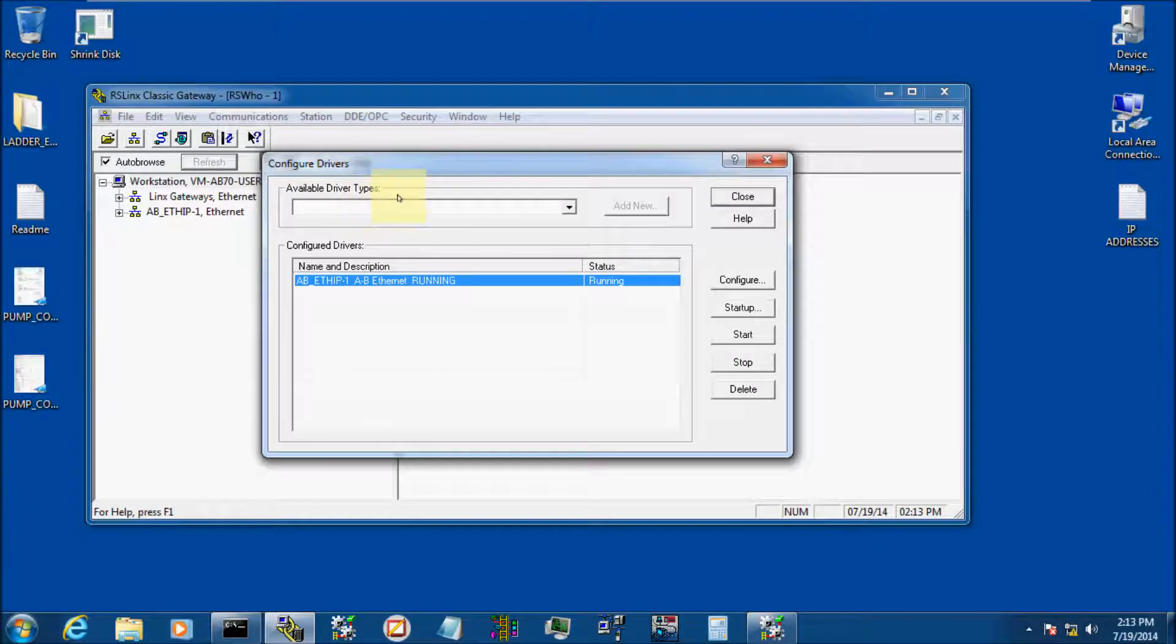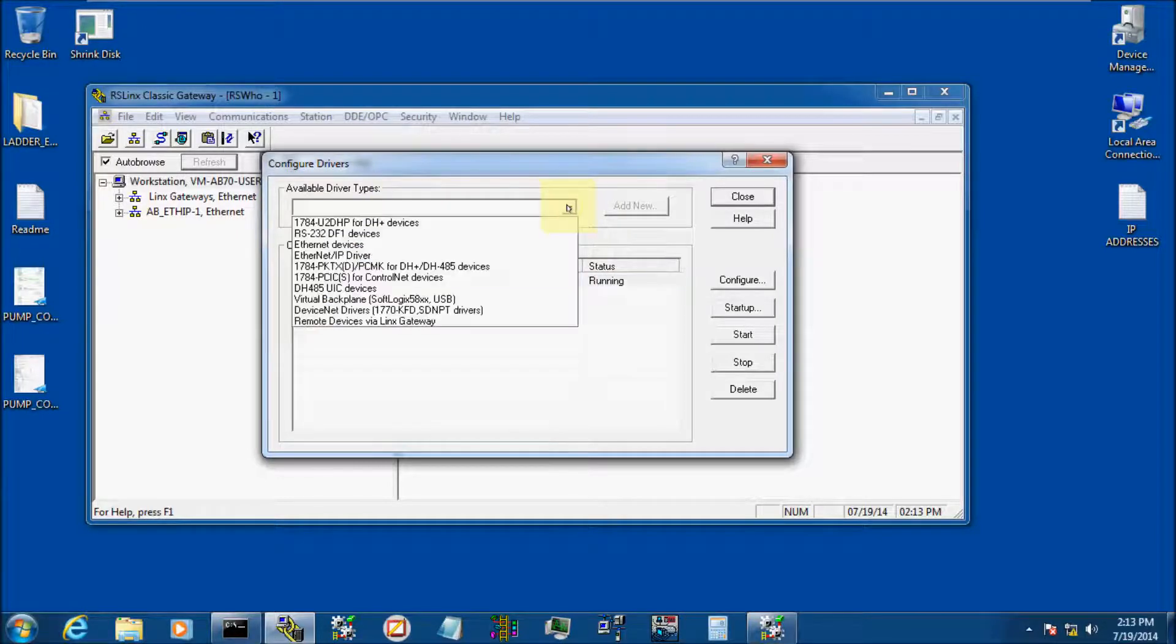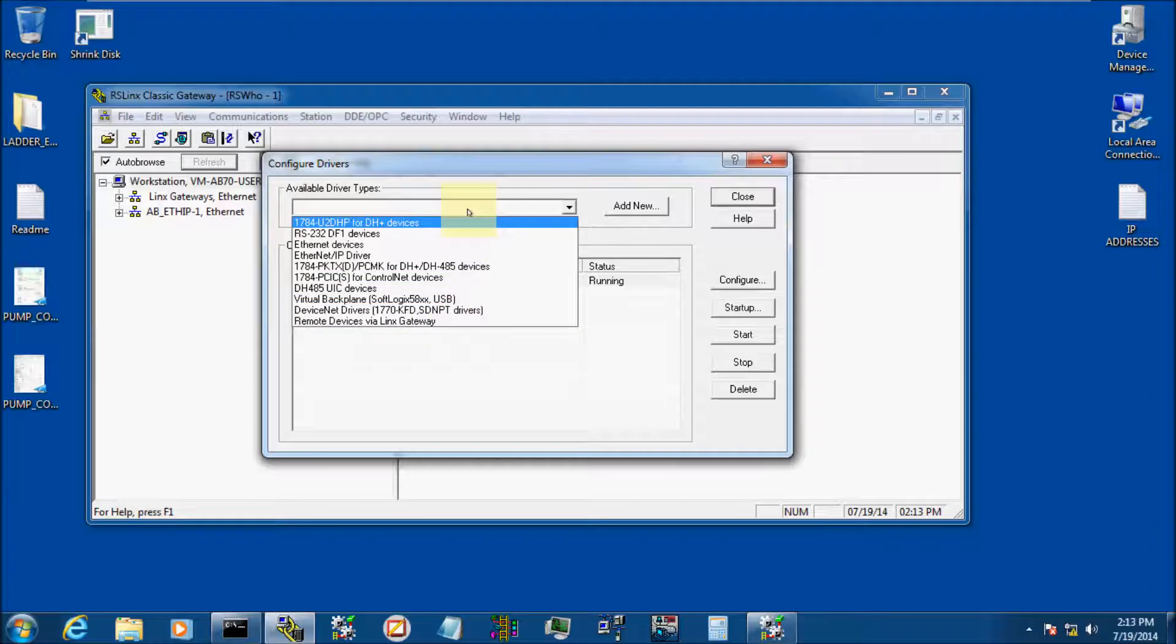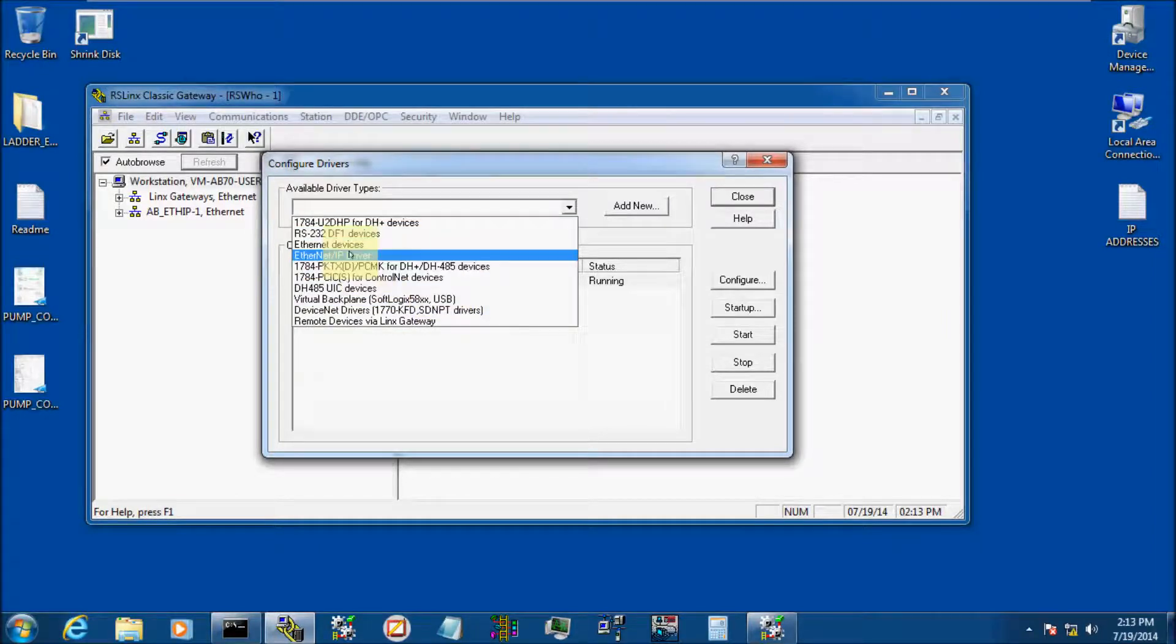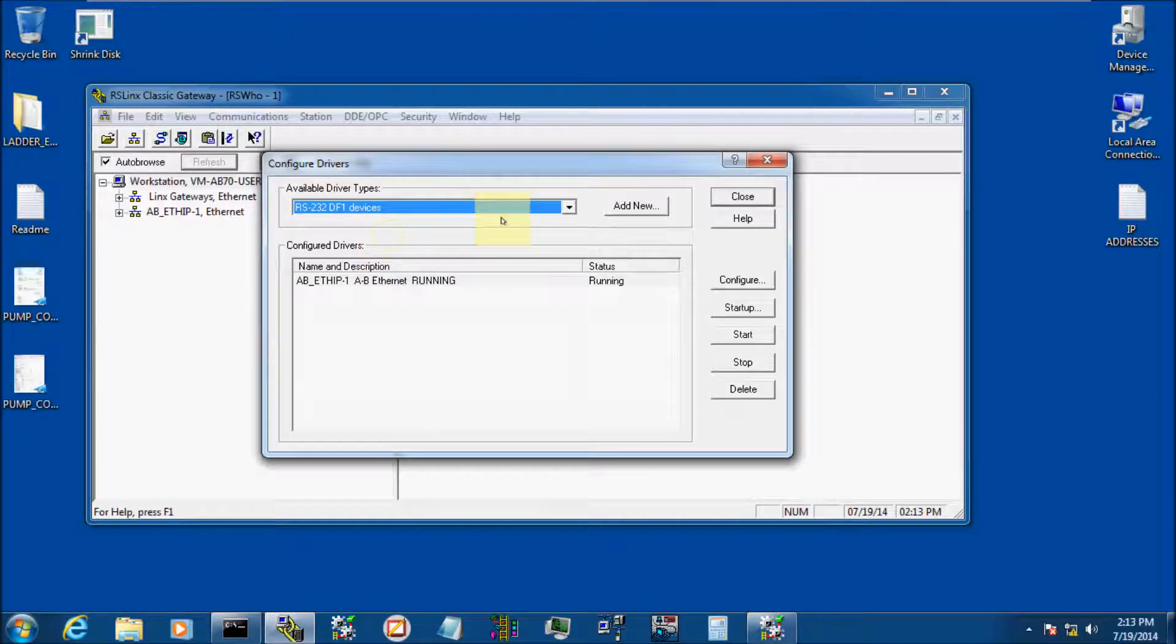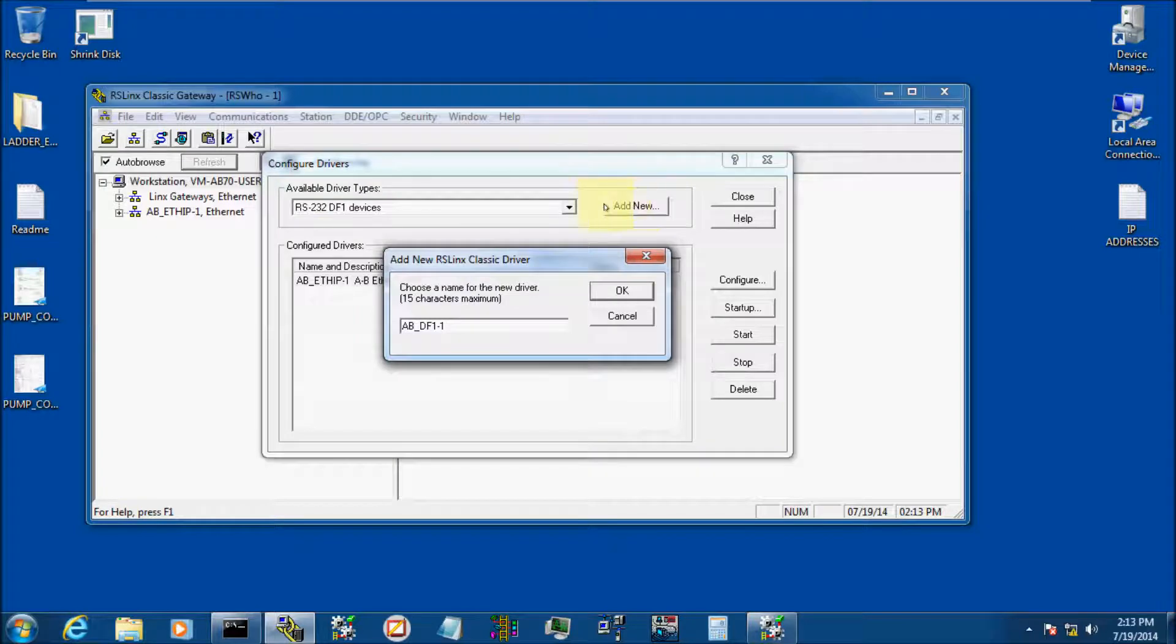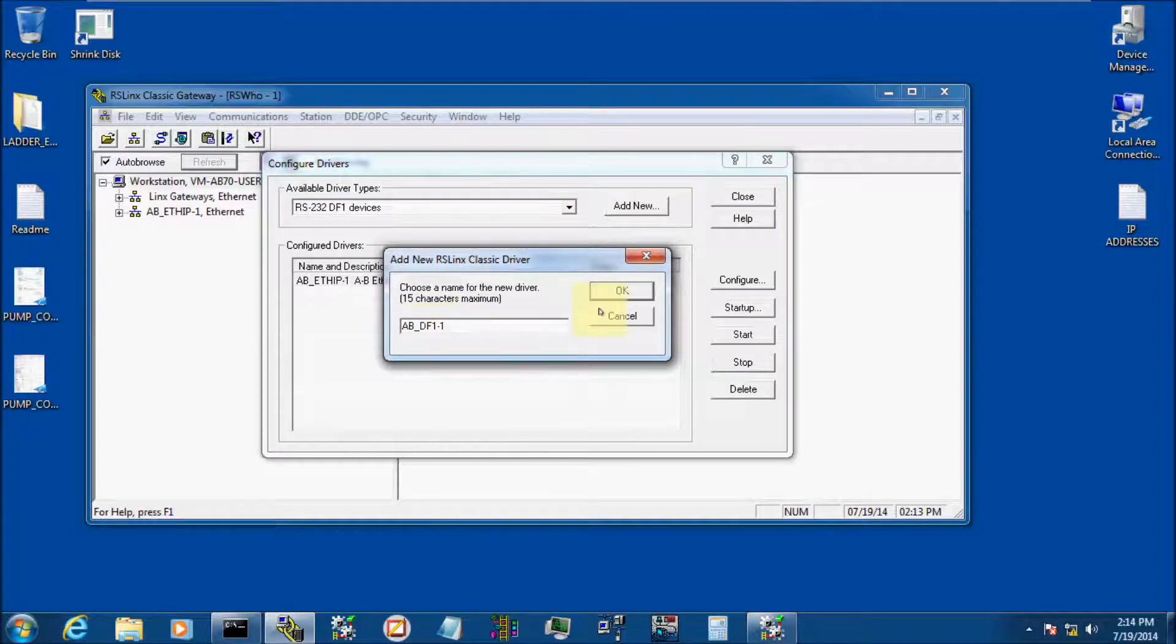When we configure drivers, we see we have the Ethernet IP driver configured and running. We're going to click on Available Drivers, and here's all the drivers that are available to you to configure to talk to something with RSLinx. We're going to use the RS-232 DF1 devices and click Add New. It's going to give you a name, whatever you want to name it. I like to leave mine in the default, the ABDF1, and I'm going to click OK.